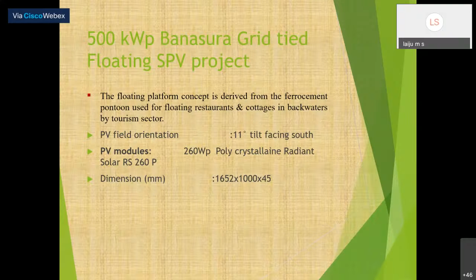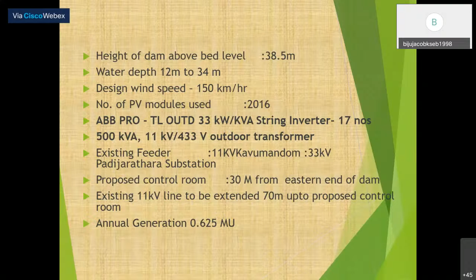So how many floats are there? The floats come to 17 plus 1, that is 18. So the 18th float holds the control room, transformer, and other accessories. Why do we require a transformer? Since the power is 500 kilowatt, we have to step it up to 11 kV. The 433 or 415 volt which is available at the inverter output point should be stepped up to 11 kV to connect it with the grid. So for grid interconnection, the LT should be stepped up to HT level, or 11 kV, based on regulation also. So please move to the next slide.